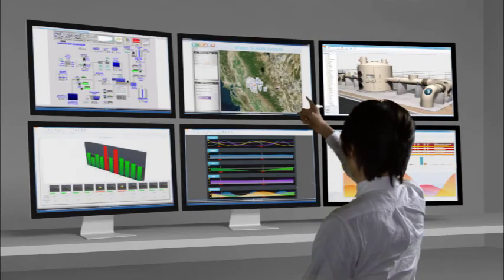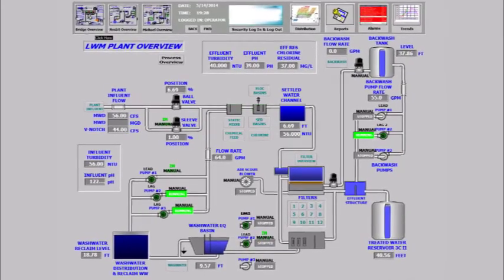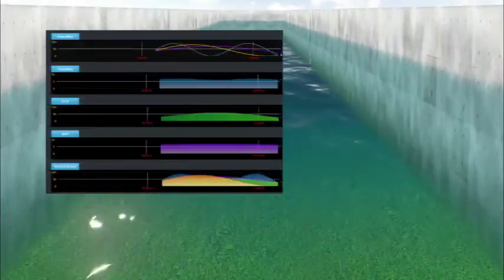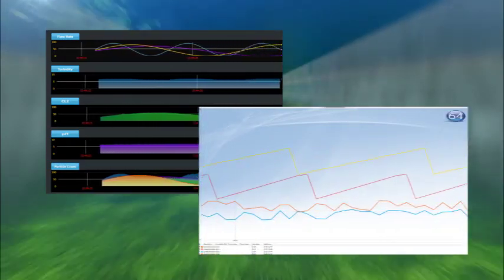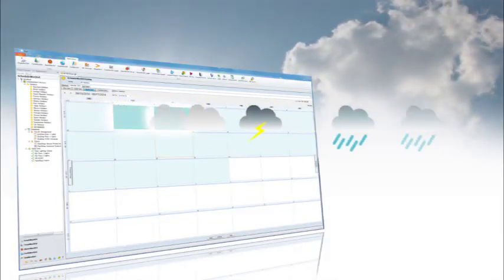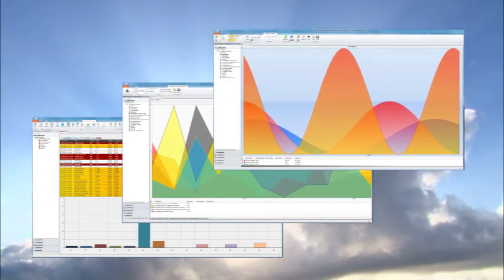All data is constantly recorded, allowing the operator to analyze things such as why a problem occurred and if it could have been predicted. By analyzing the load condition of the pump, the operational state of devices, and external factors such as weather conditions and amount of rainfall, the cause can be identified and measures can be considered. Based on this analysis, new procedures can be established to improve operation efficiency.